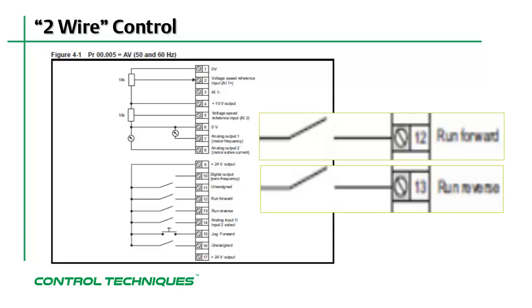In this mode, the drive sequencer functions are not latched. That means that whenever either the run forward or the run reverse terminals are deactivated, the motor will come to a stop.